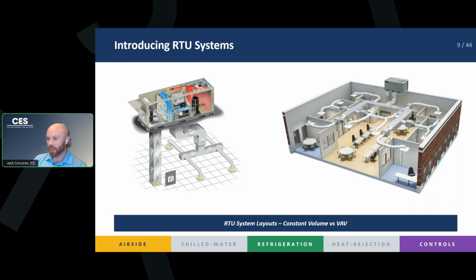Now, a key distinction here, right? Last week, again, we talked about VRF systems. VRF systems send refrigerant throughout the building to each zone to control the temperature, whereas rooftop units send air via ductwork throughout the building. So those are the two key distinctions here. We use the same three loops, but instead of sending the refrigerant through piping, we're sending air through ductwork throughout the building, right? We'll dive into that a little bit more later on.